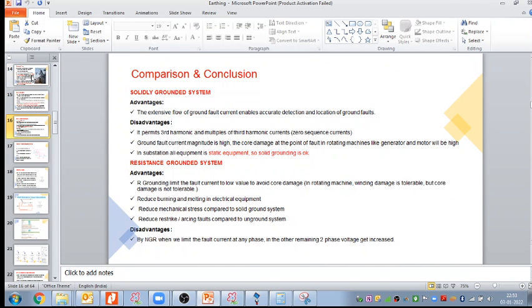Now let us conclude this discussion with a comparison. Thereafter we do the conclusion. Solidly grounded system: the extensive flow of ground fault current enables accurate detection and location of ground fault. That is the advantage of a solidly grounded system. Disadvantage: it permits third harmonic because it permits line to ground fault, meaning it permits zero sequence current. It means it permits the third harmonic current and multiples of the third harmonic current, the zero sequence current. This is one disadvantage, and the third harmonic and its multiples are more dangerous for rotating equipment, not static equipment. Ground fault current magnitude is high.